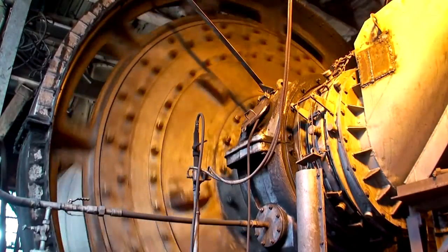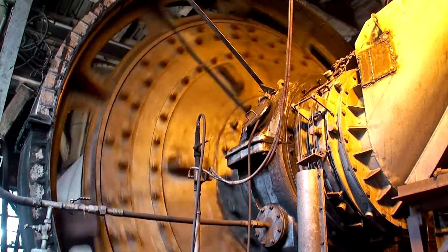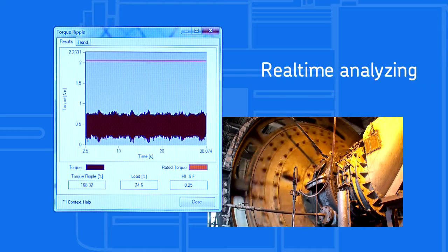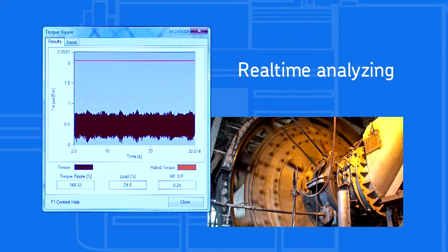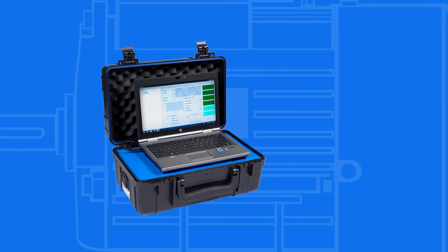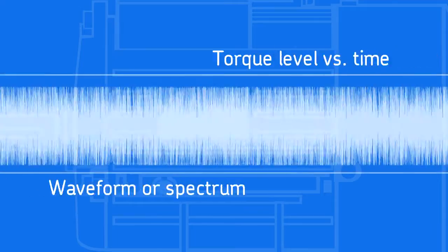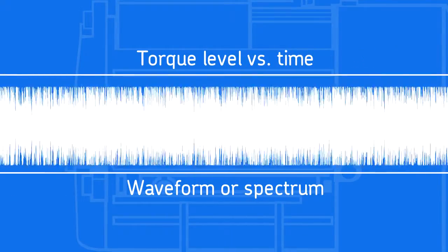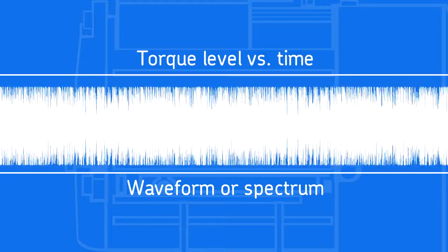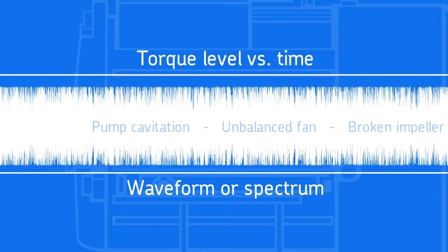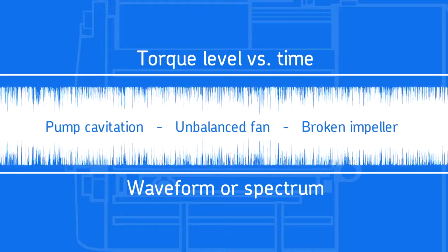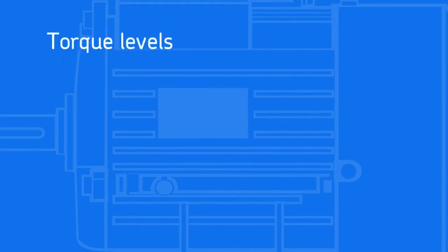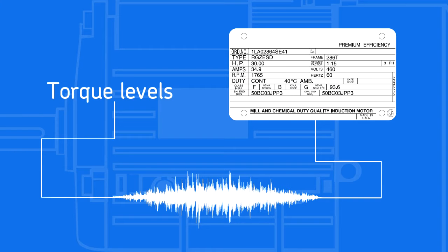Ideally, these loads do not overload the motor, even temporarily. By measuring electric motor torque, the machine load can be examined in real time. SKF Dynamic Motor Monitoring Solutions electrically measure the motor speed and torque. The torque is displayed as torque level versus time as a waveform or as a spectrum. Both are useful in determining if there is an overload condition or a load fault such as pump cavitation, an unbalanced fan, a broken impeller, etc. Torque levels are compared to nameplate values for quick identification of problems.